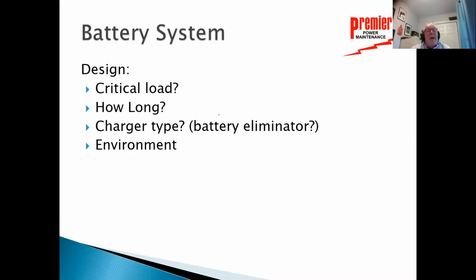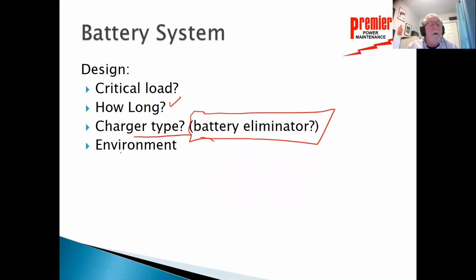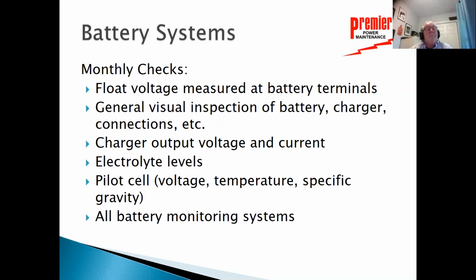How long is that battery to last? Okay, so how long of an outage do you stand, and when do you want it to be able to perform? Back in my old utility days, our batteries were designed to last for a 12-hour period. No power, 12 hours, carry all the load, and after 12 hours still be able to operate anything. What kind of charger do you have? What kind of monitoring on that charger do you have? Is it a battery eliminator so you can actually do some battery maintenance in good weather? And what kind of environment do you have that battery in? Those are all questions that need to be looked at during the design of the battery system.